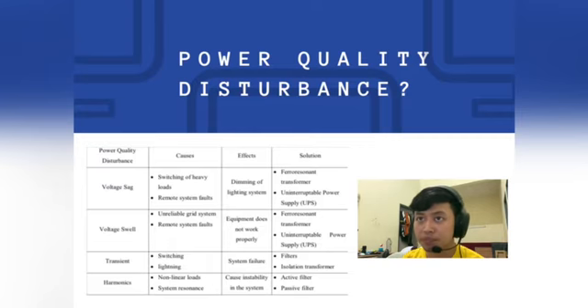Next is the transient. In some cases, it is known as a voltage spike. It is a high overvoltage disturbance that lasts only a short time. To differentiate between a transient and a voltage swell, we have to look at the waveform. A transient is large in magnitude and short in duration, and we can see a spike in the waveform. Transients commonly happen during lightning strikes and sometimes during switching. The effect is that it attacks the system, so we can have a system failure. For the solution, we have to apply filters and use an isolation transformer.